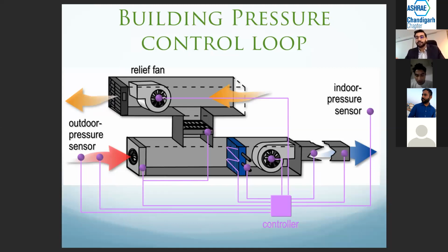Either the building is negatively pressured or positively pressured. If the building is negatively pressured, everything is just being sucked in. That is when the door won't open when you're trying to enter the building. If the building is positively pressured, everything is just trying to go out. Surgery rooms are great examples of positively pressured spaces. Similar thing here: there's a pressure sensor inside the building and outside the building to determine the pressure, and we modulate the relief fan to make sure that our pressure readings are not too positively or negatively pressured.